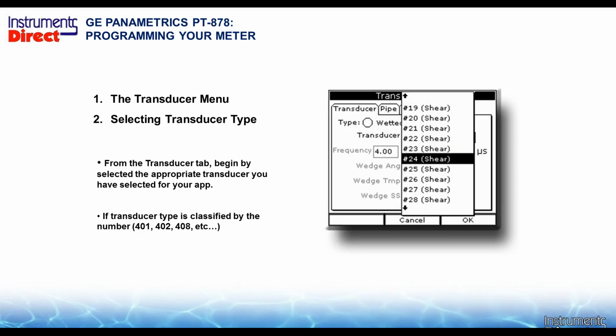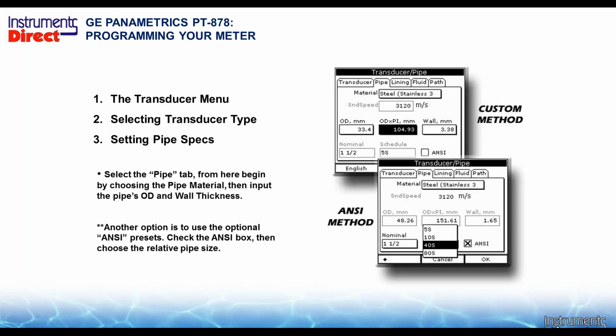If you have an older model and a newer transducer, many times the firmware can be updated to accommodate that. If it is an ancient PT878, then sometimes you can't. So we need to take a look at the serial number or age of the device to see what you can and cannot do. If you don't have that function, there is a special workaround so that you can put in any transducer regardless of the firmware. So we select the transducer, and the most common transducers you're going to see today are the 401, the 402, and so on.